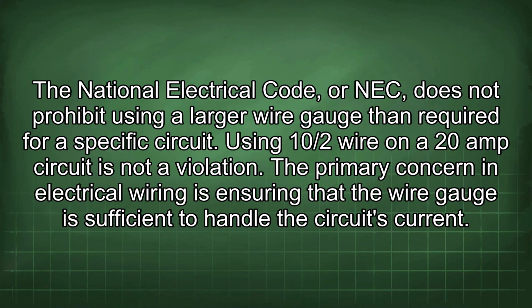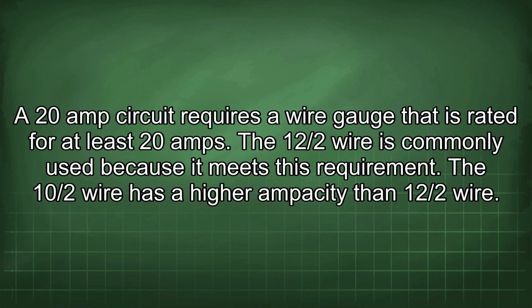The National Electrical Code, or NEC, does not prohibit using a larger wire gauge than required for a specific circuit. Using 10/2 wire on a 20 amp circuit is not a violation. The primary concern in electrical wiring is ensuring that the wire gauge is sufficient to handle the circuit's current. A 20 amp circuit requires a wire gauge that is rated for at least 20 amps. 12/2 wire is commonly used because it meets this requirement. 10/2 wire has a higher ampacity than 12/2 wire.